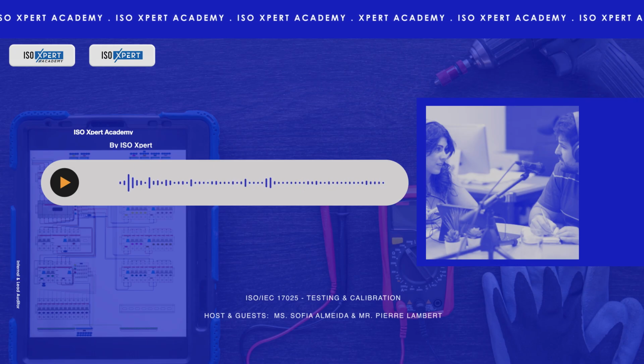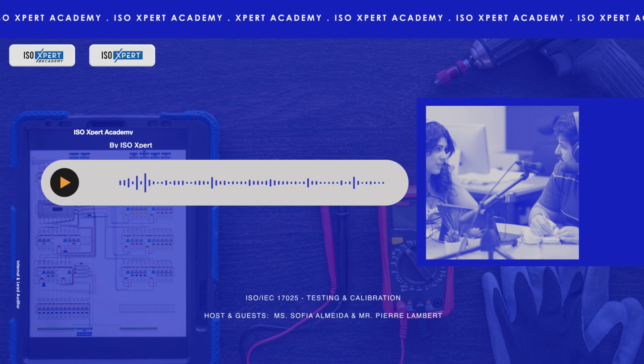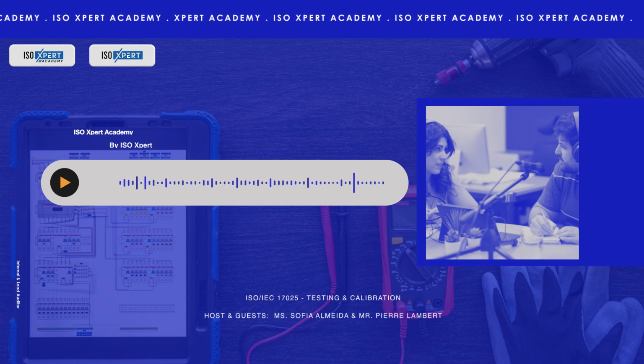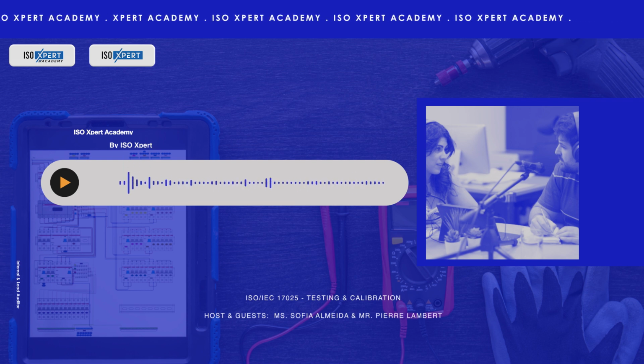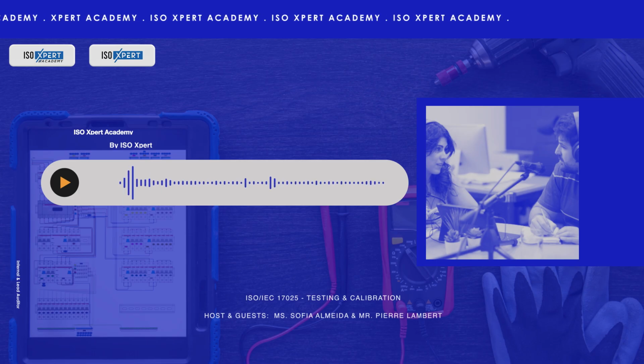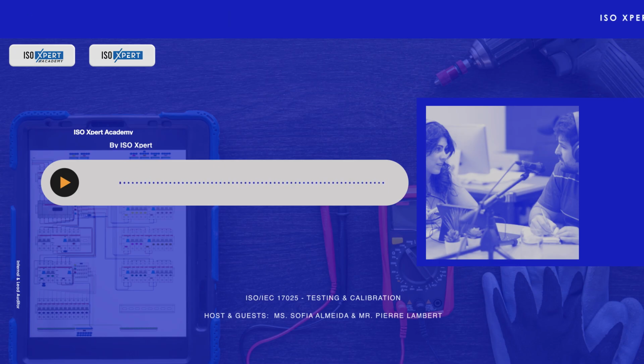Okay, so the environment's controlled. What about the tools themselves? 6.4, equipment. Yes. The objective here is clear. Make sure every piece of equipment is suitable for the job, it's properly calibrated, and it's meticulously maintained. So auditors dive into the equipment register, that master list of everything the lab uses. They check calibration certificates. When was it calibrated? By whom? Is the calibration provider accredited?